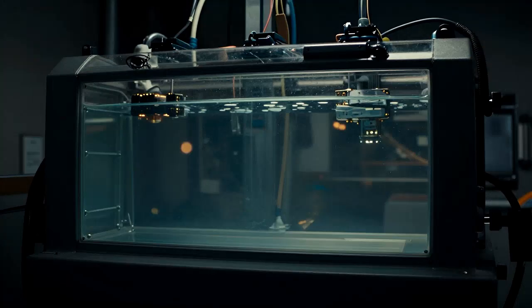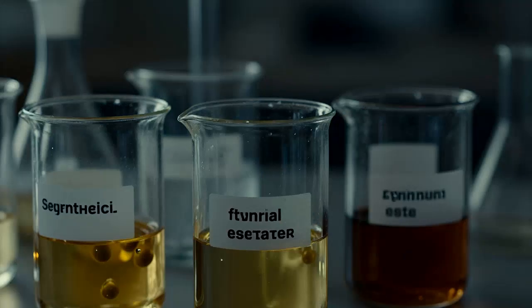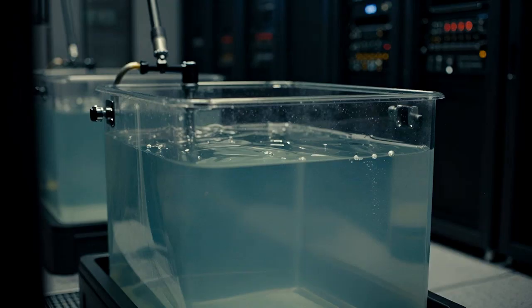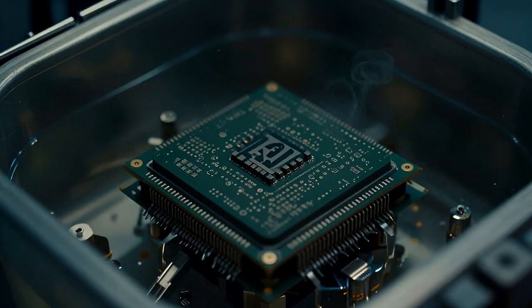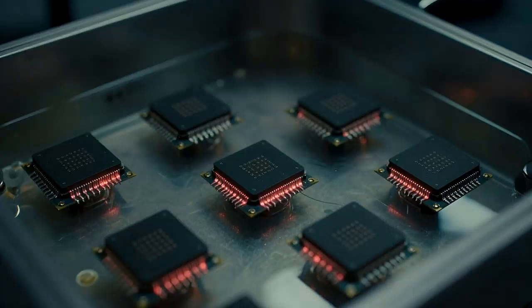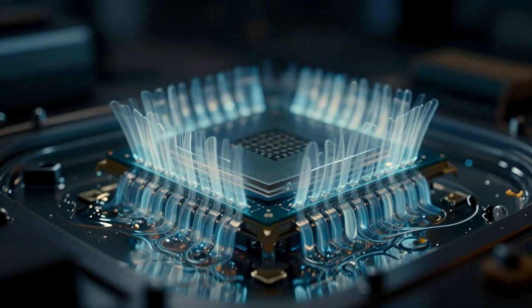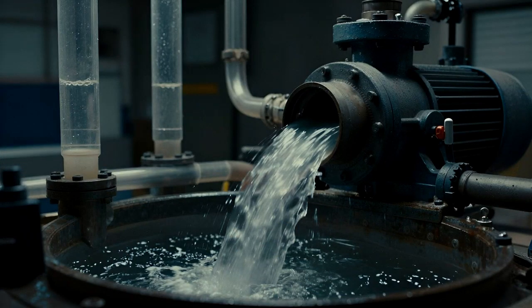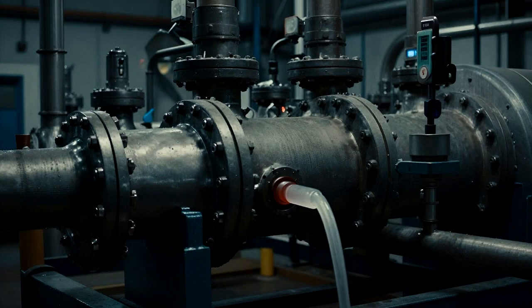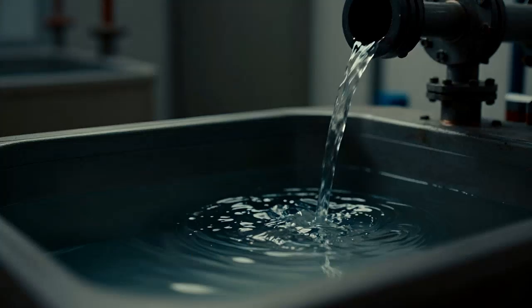In single-phase immersion cooling, the defining characteristic is absolute thermal stability. The dielectric fluid utilized, typically a hydrocarbon-based synthetic oil, a highly refined mineral oil, or a biodegradable synthetic ester, remains in a liquid state throughout the entire operation. Crucially, the fluid never boils. As the submerged chips operate and generate intense heat, the surrounding fluid absorbs it evenly across all components. A pump then physically pulls the warm liquid out of the immersion tank, runs it through a facility heat exchanger to cool it down, and cycles the chilled liquid back into the bath.